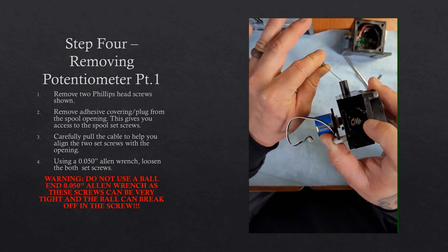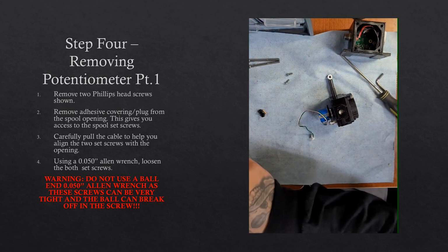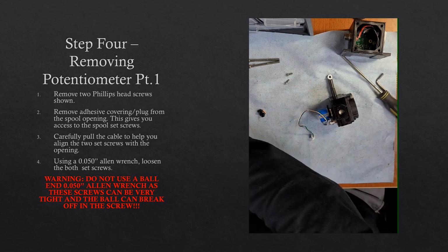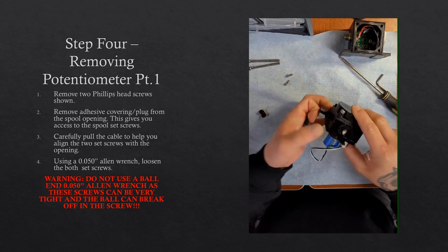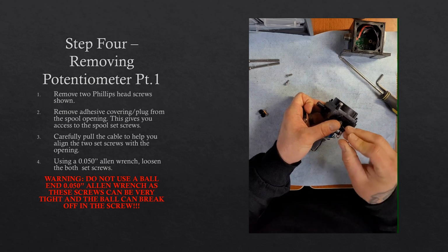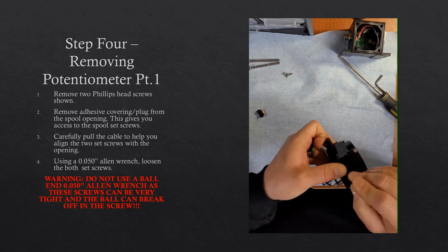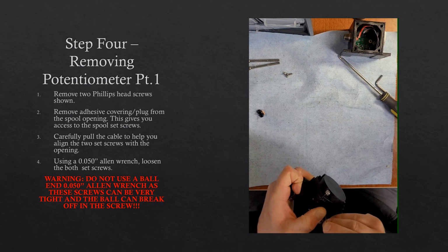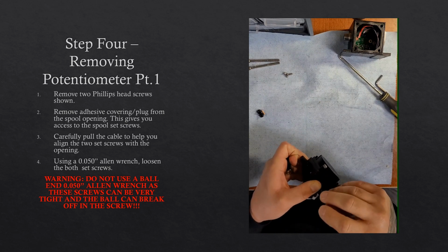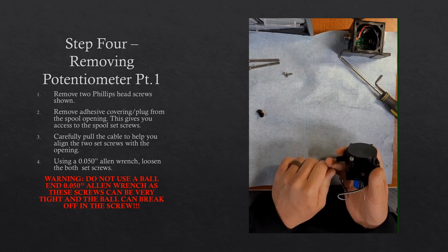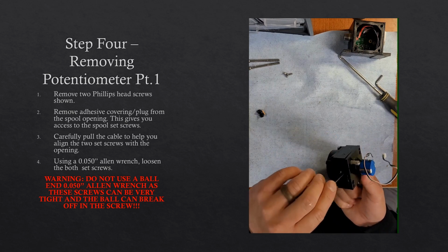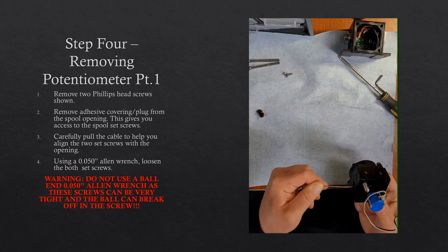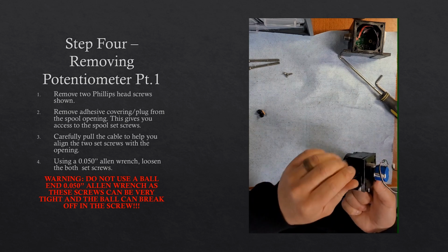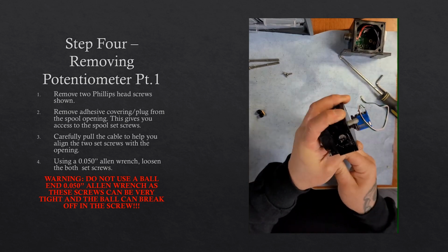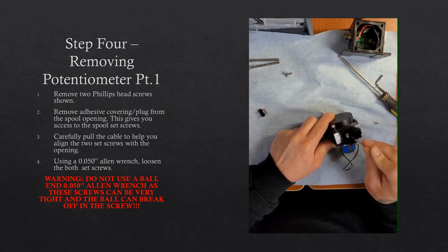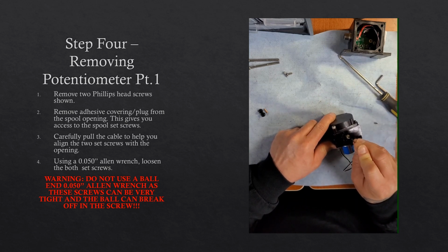To get to those set screws, you've got to pull the cable out a little bit. And we're using a 50 thousandths Allen wrench, flat end Allen wrench, not ball end. Can't tell you, some of these set screws are in there very, very tight from the manufacturer, and it will snap the ball end clean off of the Allen wrench, and that part is essentially junk. So make sure you use a flat face 50 thousandths Allen wrench to loosen those set screws. You can see here I'm struggling with these ones even. So yeah, make sure you don't use a ball end or it'll snap off in the end.